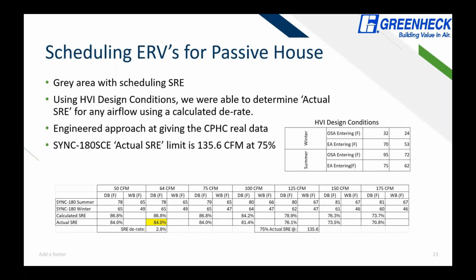Now, using the highlighted actual SRE, that highlighted number right there is an HVI data point. So at 64 CFM, at 32 degrees outside, with those HVI design conditions specifically, we were able to determine what the core simulation data is. I was able to calculate the SRE at that 64 CFM, and then I was able to get what the derate is for basically the other losses in the unit, which includes temp rise from the fans, the static pressure from the filter, etc. So I was able to determine here's the actual SRE for the other airflows, and we can also determine that using that derate, your maximum airflow with this unit and still achieving a quote unquote 75% actual SRE is about 135.6 CFM.